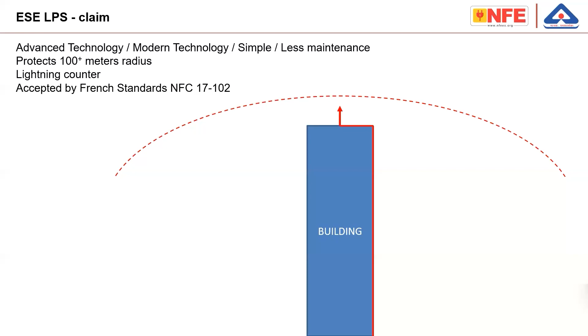Now, please note that lightning protection is not about a rod or conducting the current through one conductor and sending it to soil. We are talking about a very high current flow through a very small duration. The current is going to jump to all the nearby metallic objects. It is going to get coupled to the metallic installation. So we have to have a very good equipotential bonding as well. Once it comes to this non-standard lightning protection called early streamer emission sold in India, for example, solar PV installations, almost 99.9% of solar PV installations are made with early streamer emission devices. I will show you how this becomes illegal in India in a later slide.